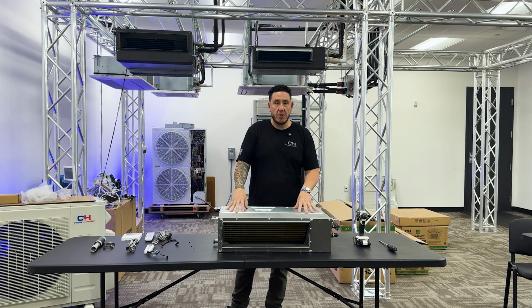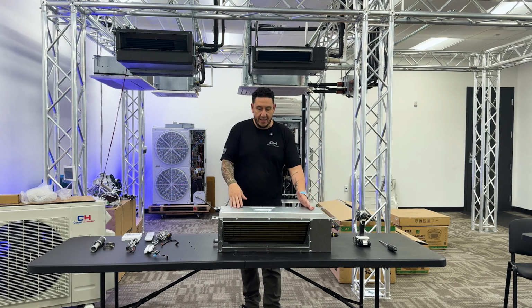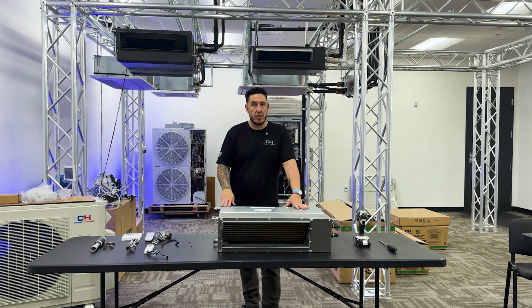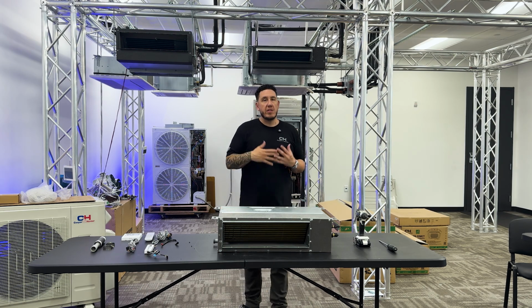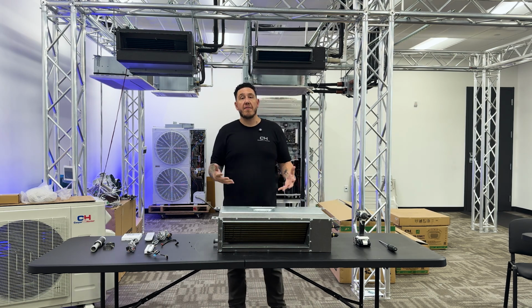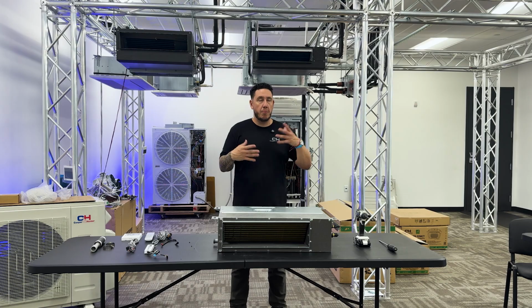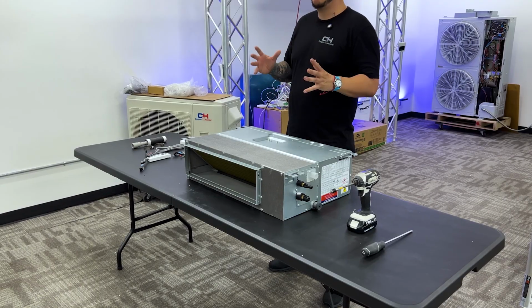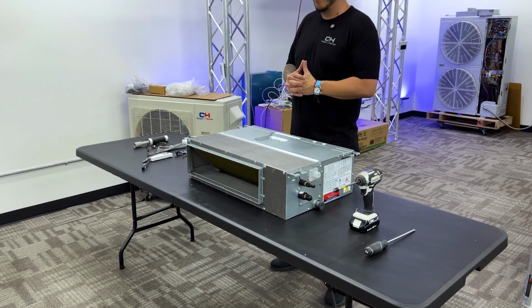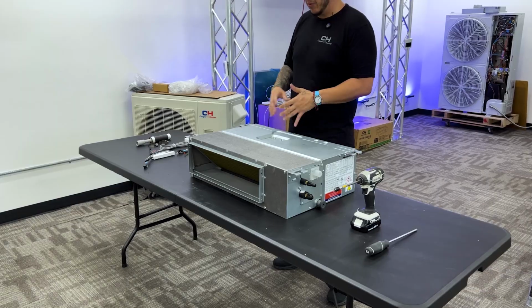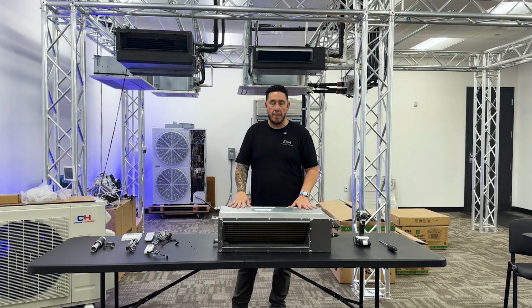On your smaller systems, between 9 through 18,000 BTU, they're medium static pressure units. From 24 to 60,000 BTU, we have high static pressure systems up to 0.84. You're going to have metal fan blades because it is a high static pressure unit on our 60,000 BTU. On all the other ones, you're going to get a plastic blower wheel on the assembly.